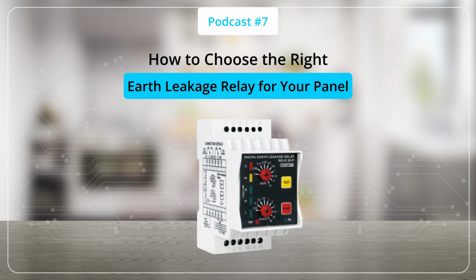The second factor is time delay. Time delay settings help prevent nuisance tripping caused by temporary or transient currents. Depending on the application, delay settings may range from instantaneous operation up to 10 seconds. The third factor is the relay type and waveform compatibility. The selected relay should match the type of load being protected. Applications involving VFDs may require Type A or Type B relays capable of detecting more complex waveform characteristics.